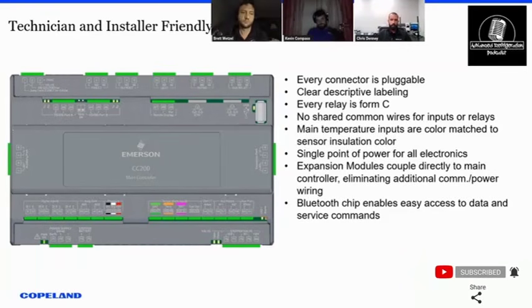Same thing on single point of power for everything. So we're just gonna use one power supply. It's actually 24 DC instead of AC for this controller. Switching to DC helped us pull off being able to do all those stepper valves, expansion modules, and the display, everything on one. So you just hit the power plug down in the bottom left, and then the power is distributed out through the side connectors.